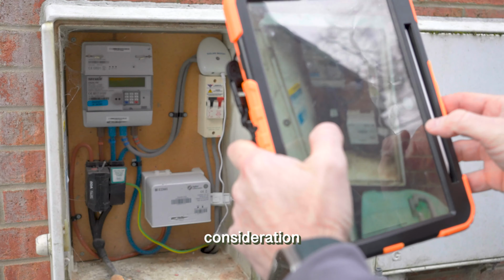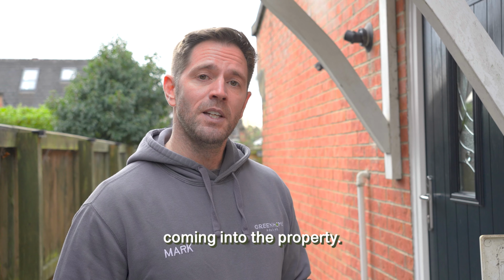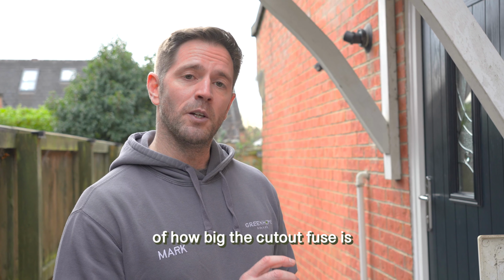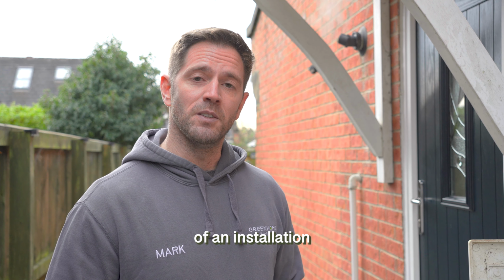Another important consideration is the electrical supply coming into the property. So we need to make note of how big the cutout fuse is supplying the property so we can notify the DNO of an installation of a heat pump.